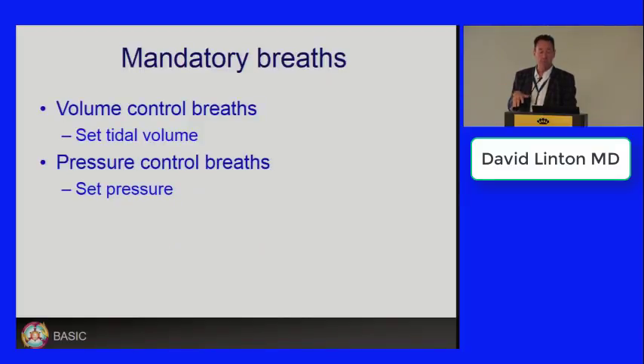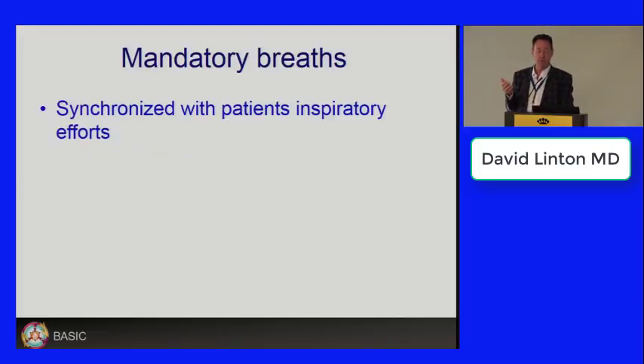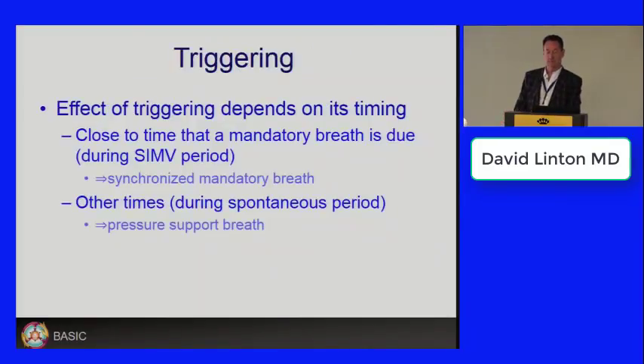Mandatory breaths are volume control, the spontaneous breaths are pressure controlled, and they synchronize with the patient's breathing. If the machine is set with a very good trigger sensitivity and has a good demand valve, then the person can breathe and synchronize both the mandatory and the spontaneous breath, and it's the most comfortable.